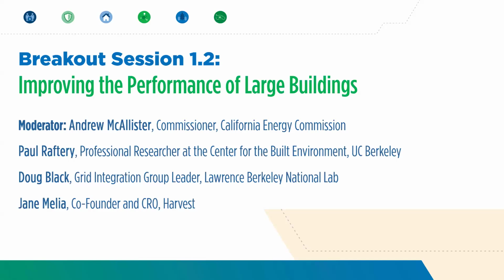Great question. Certainly the efficiency work will help with sizing. At the very least, it will help you understand better what the loads are in the building. A lot of equipment is oversized just because boilers are so cheap. Boilers in large buildings are sometimes on a rooftop, but a lot are in a plant room. Generally it's very unlikely you'll be able to site something in the same place without some structural upgrade, since the equipment is much larger. There are some cases where you can, but for the majority, fully electrifying is a bit challenging.